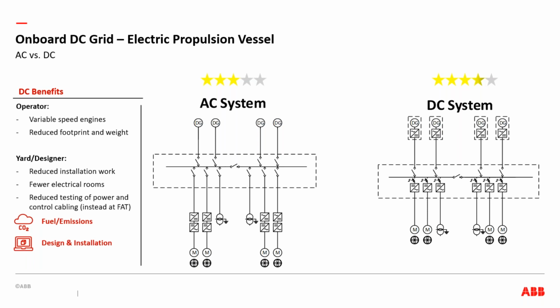There's also the potential to reduce footprint and weight. Traditionally with AC systems, variable frequency drives are scattered around the vessel, which is flexible since you can place them where needed. But the downside is redundancy in the cooling systems and the need to provide cooling to those units, and if the drives are in the engine space, that's not a great environment for electrical equipment. With the DC grid system, we take all those converters — usually the rectifiers, even though shown with the generators — and move them into one lineup, in one cabinet, which can expand or shrink depending on vessel size. It's all in one small footprint.